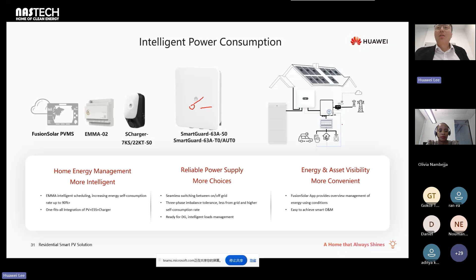First one is Smart Guard. Smart Guard has two versions. One version, S0, is for a single phase, and the T0 is for three-phase scenarios. Maximum, it can connect to the off-grid backup power, and connect up to three inverters in Smart Guard. When a fault occurs, you can manually bypass the module, and it can control the switchover in 20 milliseconds.